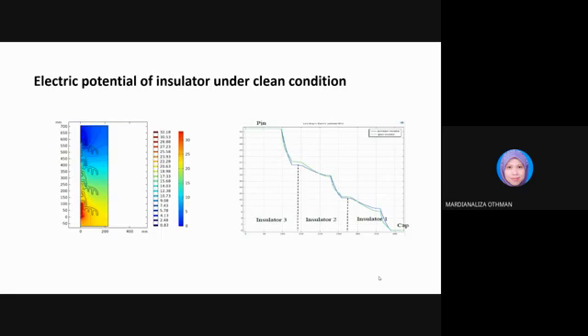As the distance of the insulator unit to the ground of the string decreases, the voltage distribution over the unit also decreases. The voltage distribution of an insulator closer to the high voltage line conductor was reduced 38.79% from 33 kV to 20.2 kV by decreasing the insulator unit's distance from insulator 3 to insulator 2. In contrast, when approaching the insulator cap of insulator 2, the voltage distribution dropped to 13.3 kV. This is because the insulator's bottom end was connected to the high voltage conductor in the transmission line tower, while the insulator's top end was the ground.